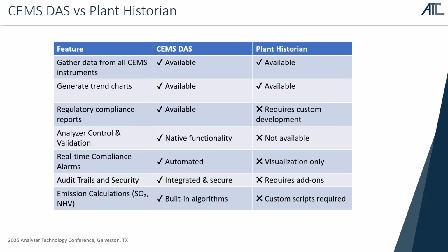Now, one of the questions I received from the reviewers when I submitted my paper, and I appreciate it, so I wanted to quickly touch on that, was the CEMS DAS, which is the generic name for data acquisition system, versus the plant historian. So if we're grabbing all this data from all these analyzers and then we're trending and reporting them, can't we just use our historian for that? And the short answer is absolutely, you can, with enough time and effort. You can build a historian to accomplish all these various nuances of the regulation.